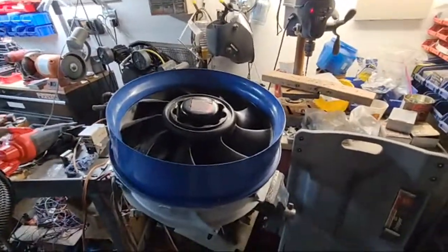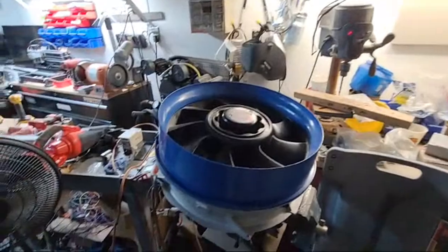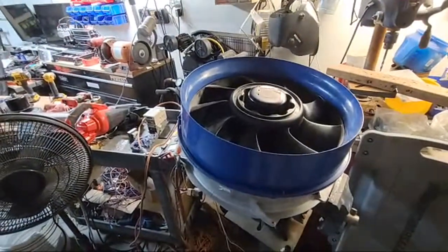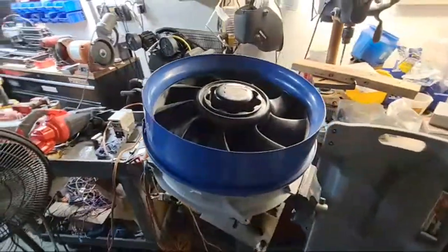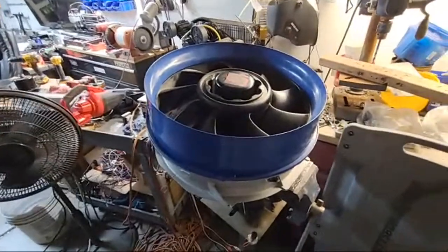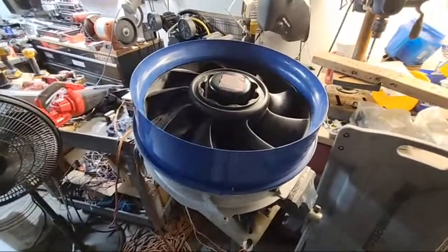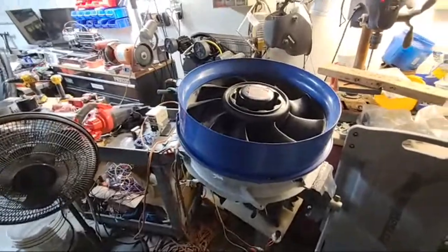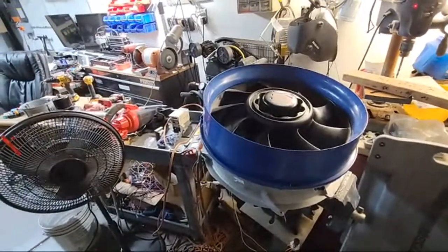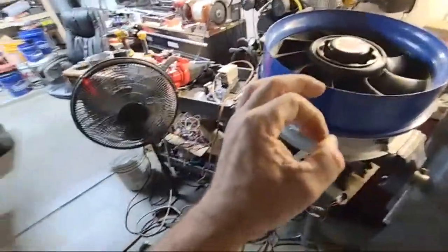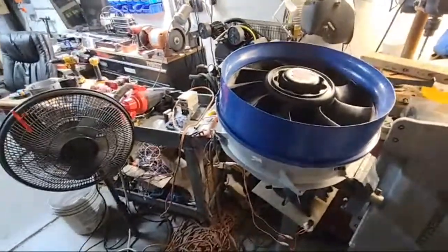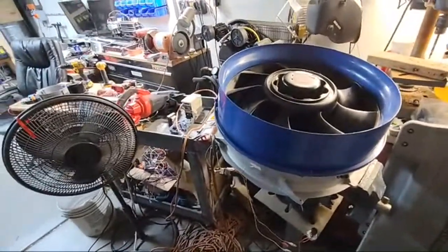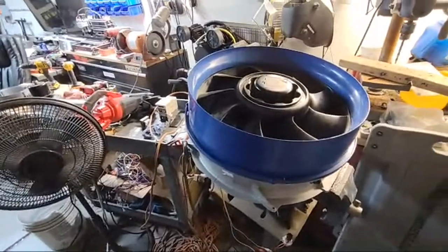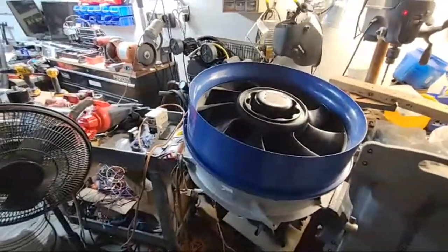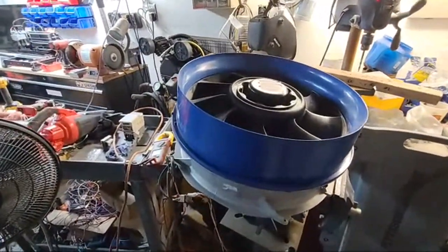It was bright, it was loud like a gunshot, and my 50 amp breaker in my main panel just would slam - boom. Tried it a couple times, boom. It was actually shocking that it did that. But that's what it had to be, because nothing past those fried traces on that circuit board was bad - there was no ground fault in those fan inverter boards, because both of those inverter boards are good, and you'll see me using them in my previous video.